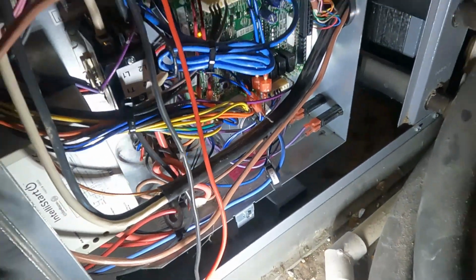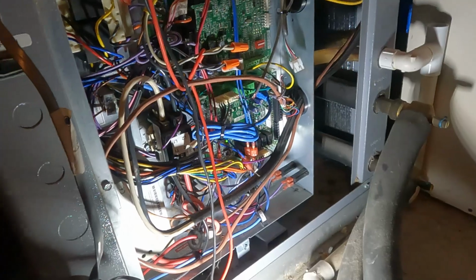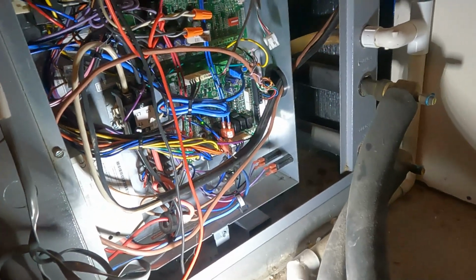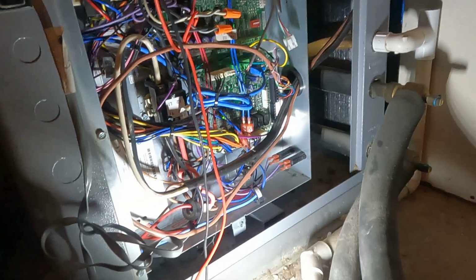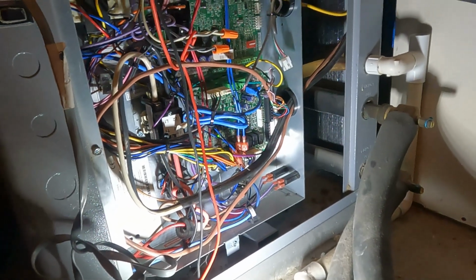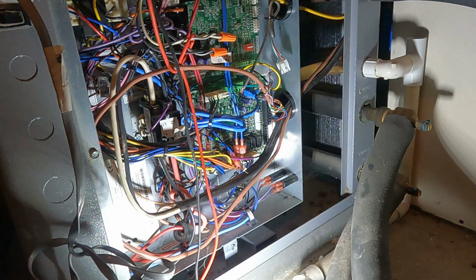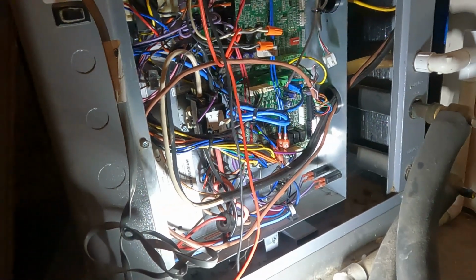It could also be something inside the thermostat itself, but this was the easy way to fix it and at least test that. I'll give the customer the option if they want to replace that thermostat, they could. If it was me, I'd recommend just leaving it in a non-communicating manner. It does the exact same thing. Still a 2-stage compressor, still stages out everything, still brings on the different blower speeds. So I'm not a real big fan of communicating thermostats for that reason with the electrical interference. I'll check everything else out and let you guys know before I leave if I find anything else.